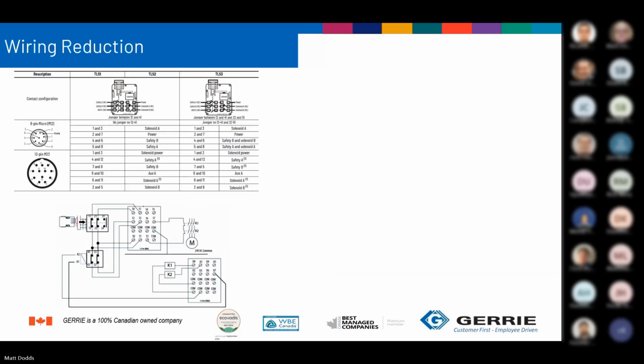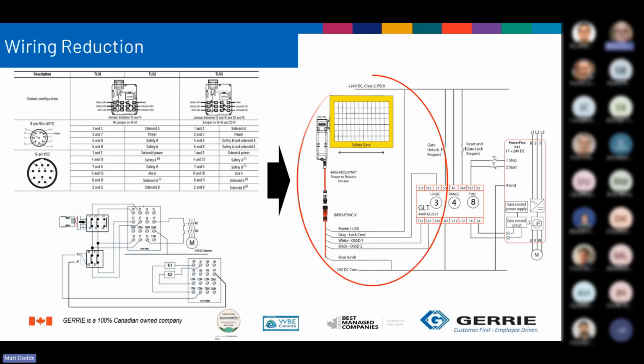Another reason I like this switch, the image shows a standard TLS door switch with lots of connections to mess up. The 440G MZ has 5 connections: plus and minus 24 volts, 2 outputs, and 1 lock/unlock input, offering a huge advantage in the reduction of the number of connections that need to be made. It's all internally self-monitored, so all the extra connections are not needed. Another side note, in the image on the right is the use of the 440R-GLT guard lock timing module, which handles all of the timing and sequencing for guard door access with minimal connections.